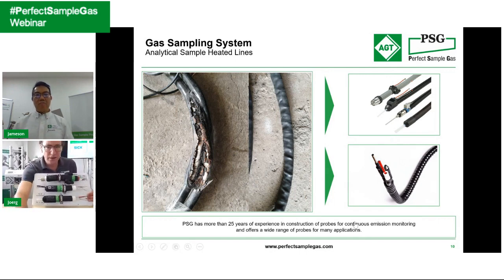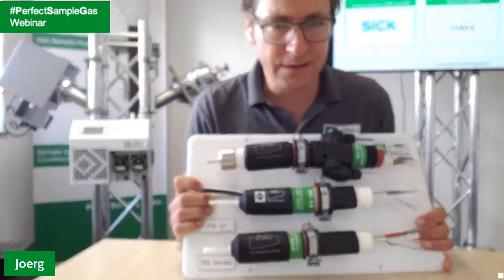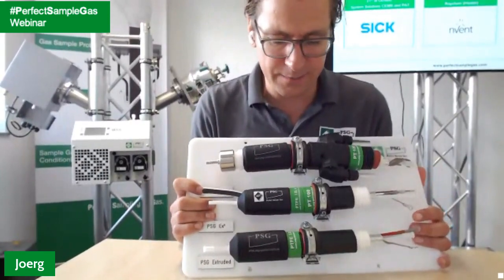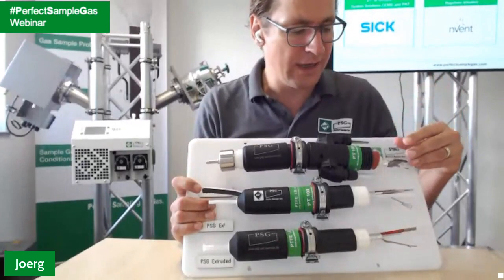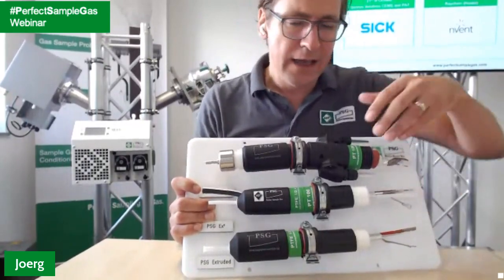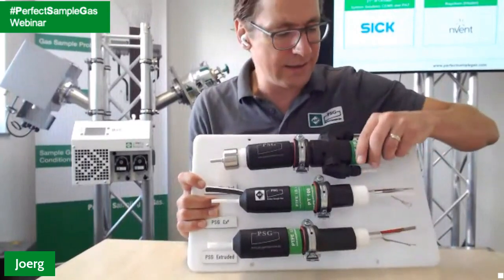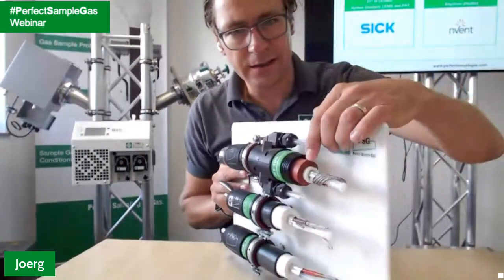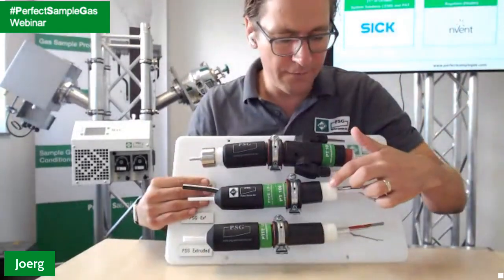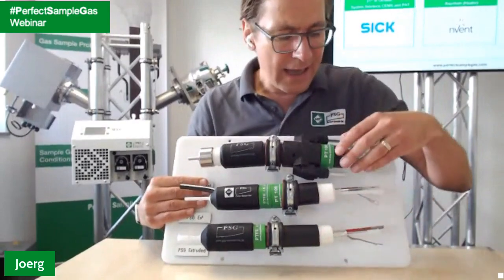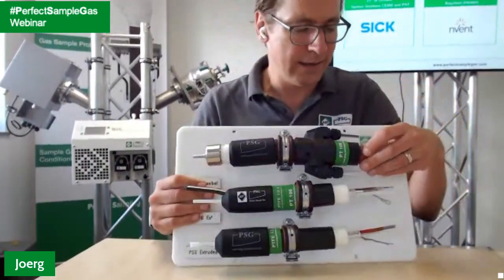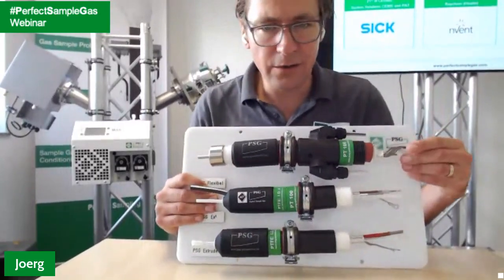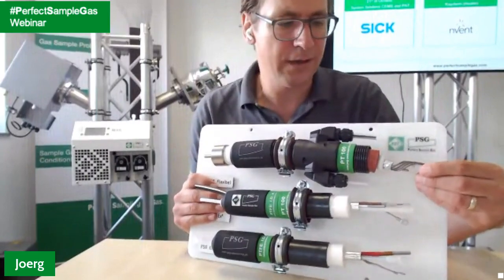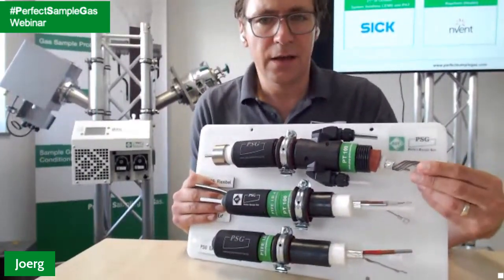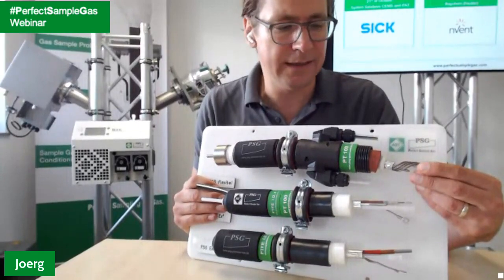So, Jameson, let me just shortly show some details of the heated sample lines, to give a little more detailed explanation, and allow me to outline what is very important here. If we talk about the flexible lines, as you can see here, the insulation comes from a different technology. Here we have a thermal fleece, which is used for these types of lines. And the fixed resistance line comes with a silicone rubber insulation. You can also see a big difference from the heating tape, meaning the electrical heater, which is responsible for heating up the heated sample line.